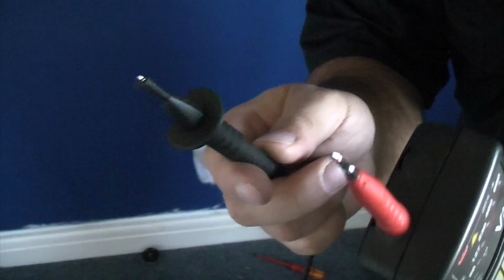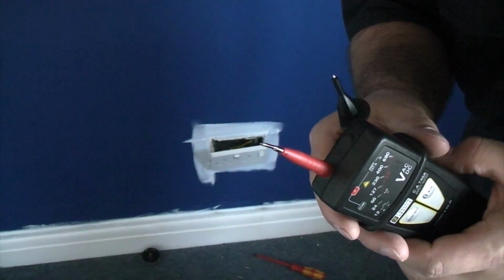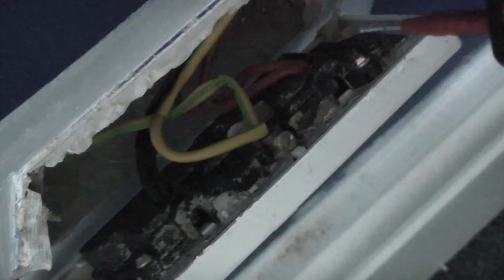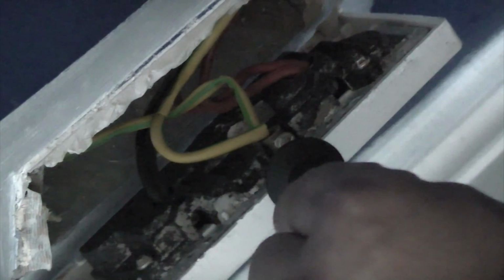So now we're going to get the two probes and we're going to test the actual socket just to confirm that it is dead. So firstly we'll test between the neutral and the live. So we'll locate that on the neutral and then touch that onto the live terminal, and as you can see there's no indication there that there's any voltage there at all. So now we'll just check between earth and live, and again there's nothing there. And then just to be on the safe side, we'll just check between neutral and earth, and again there's nothing there. Once you've done the test, you need to confirm that your meter is still working by pressing the test button. So we can be certain now that this socket is dead, so it's now safe to remove the socket and continue fitting the new one.